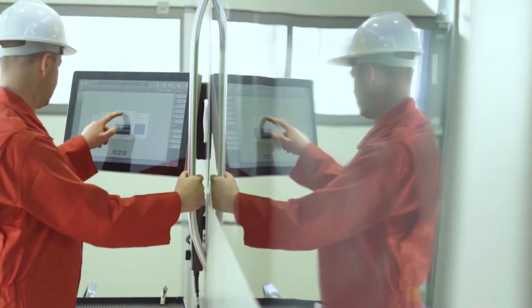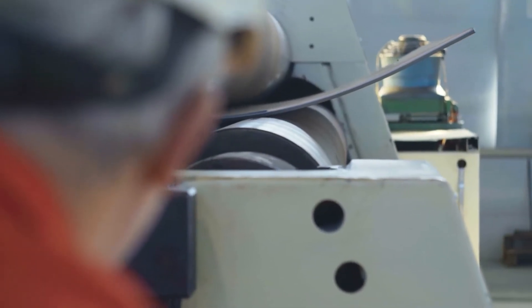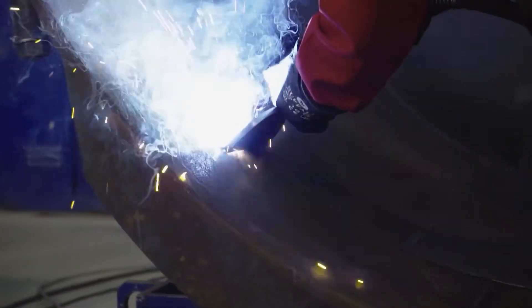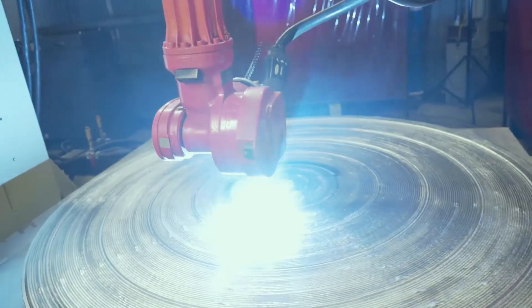Components for smaller exchangers made of stainless steel are cut by a laser. Cut parts are then formed into individual sections, which are later joined to form a shell and a front head. To increase the corrosion resistance, the carbon steel tube sheet can be weld overlay cladded with stainless material.